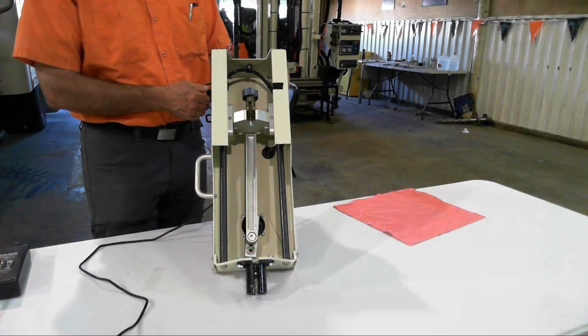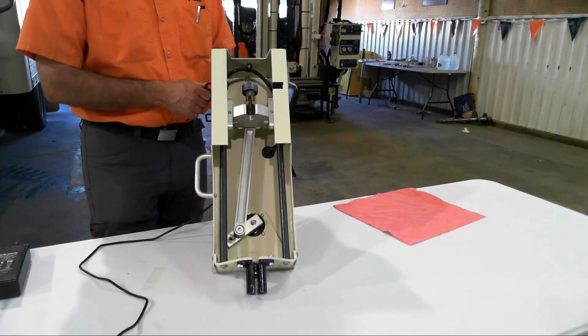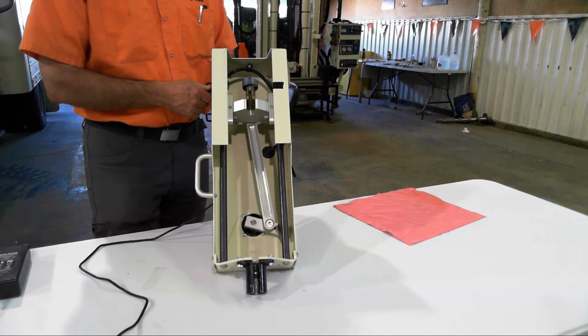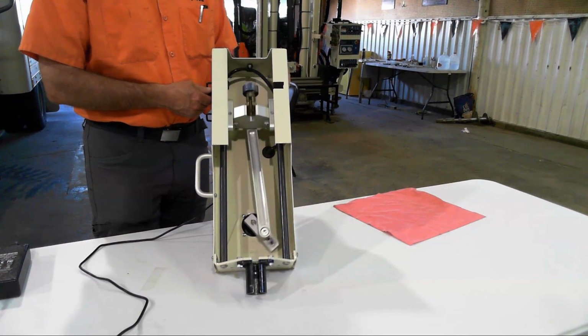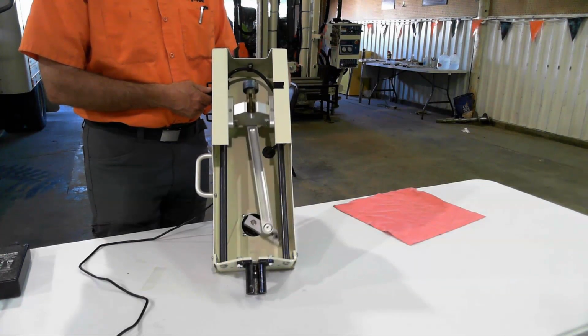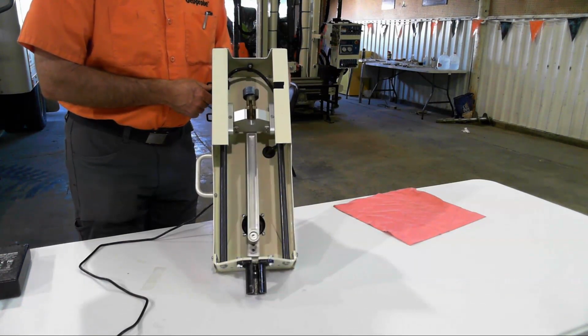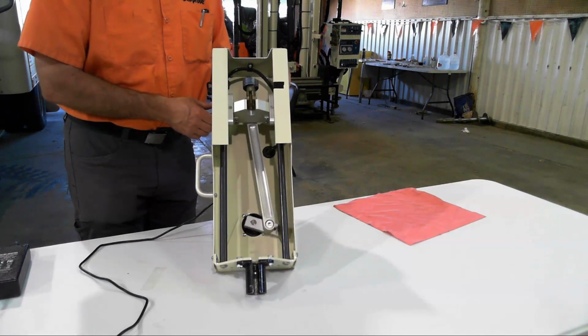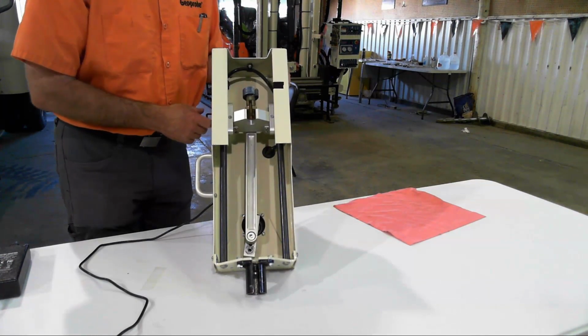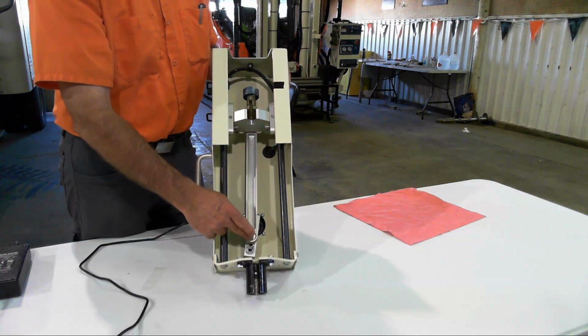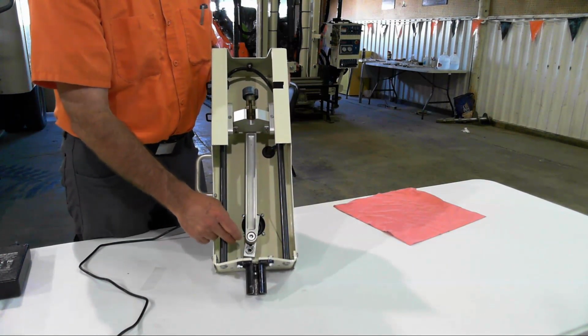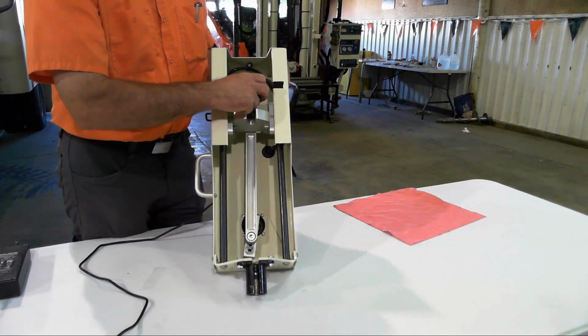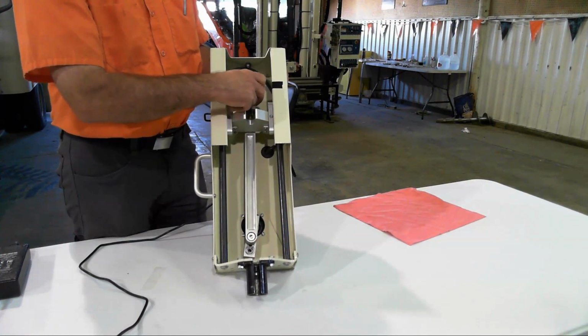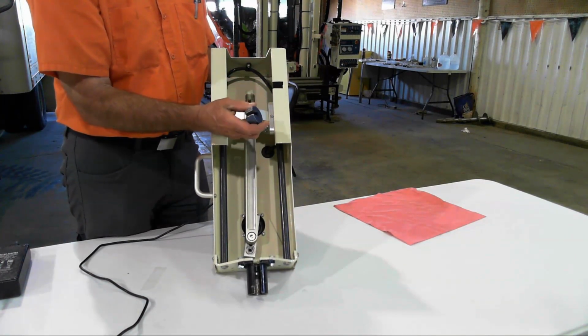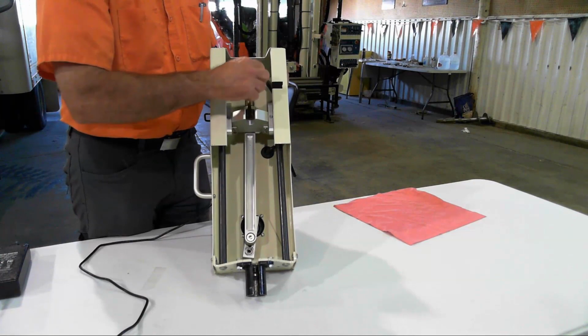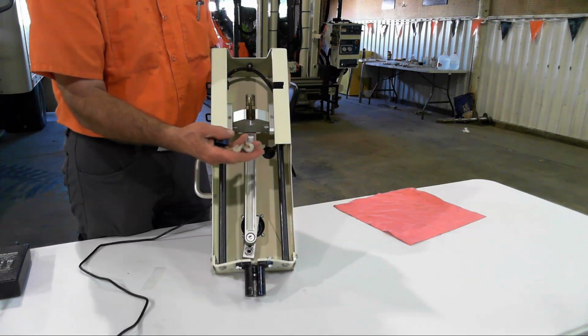Sampling will be done using the mechanical actuator on the rods. You should have the slotted 1.75-inch rod mount on the base of the unit. You will connect to a 12-volt power supply, and the speed of the actuator can be adjusted using the rheostat on the side of the unit. You will want to turn off the switch with the actuator at the bottom of the stroke, showing the moving arms are at their lowest position, as they are here. There is a split cap with a pair of half nylon bushings which will hold the 1/4-inch tubing in place. These are being removed from the unit, and we will take a closer look at them now.